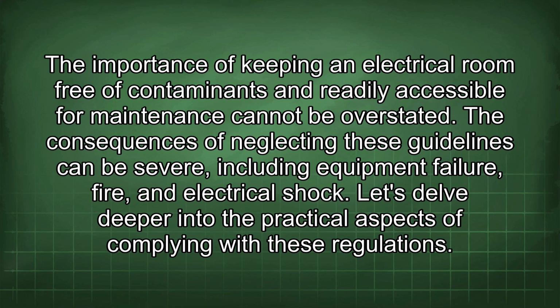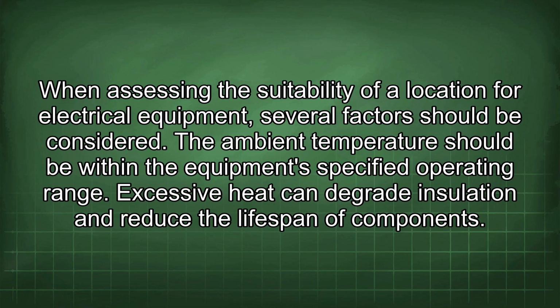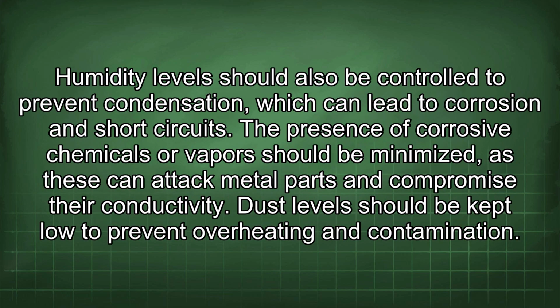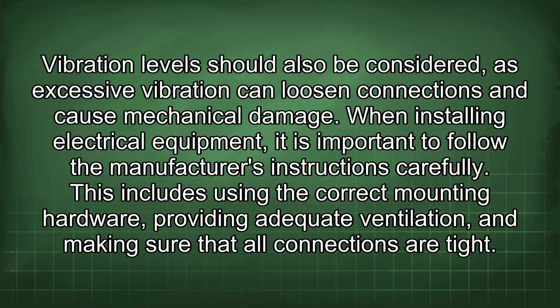Let's delve deeper into the practical aspects of complying with these regulations. When assessing the suitability of a location for electrical equipment, several factors should be considered. The ambient temperature should be within the equipment's specified operating range. Excessive heat can degrade insulation and reduce the lifespan of components. Humidity level should also be controlled to prevent condensation, which can lead to corrosion and short circuits. The presence of corrosive chemicals or vapors should be minimized, as these can attack metal parts and compromise their conductivity. Dust level should be kept low to prevent overheating and contamination. Vibration levels should also be considered, as excessive vibration can loosen connections and cause mechanical damage.